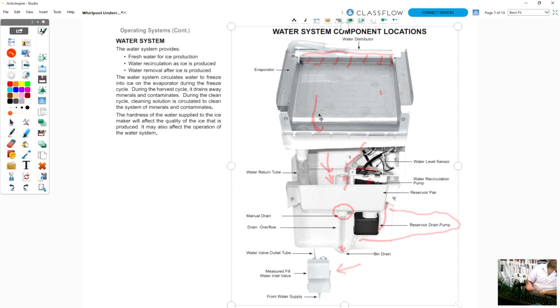As water slowly flows over it, the water itself is going to get cold and go back into our reservoir. So we're cooling down our reservoir and making it easier for the ice to produce. It should take anywhere from 20 to 30 minutes to produce one batch of ice. And if you counted how many cubes that would be, you can multiply that by 20 minutes, and it would tell you how long it would take to make about 50 pounds of ice. It's usually within 24 hours that if someone does not take any ice out of the ice bin when it produces ice, it will fill that ice bin up. So it takes about 24 hours to completely refill that unit.